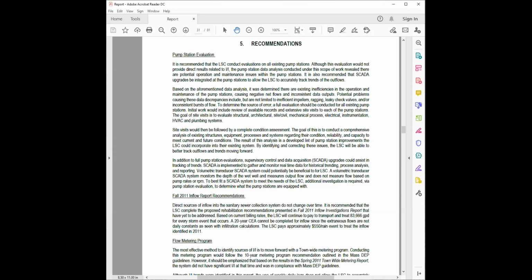Right, Pete, that's a good point. Each station would be evaluated as part of this proposal, previously given to you around May 2016, to determine what the right sensors and flow metering devices would be as part of that recommendation. But you'd definitely have real-time flow data, so the variable speed of your pumps and the things that are question marks in our calculations now wouldn't be question marks anymore. You'd know exactly what's coming out, and I presume that would immediately rectify the question about negative pumping in that one station, at a minimum.